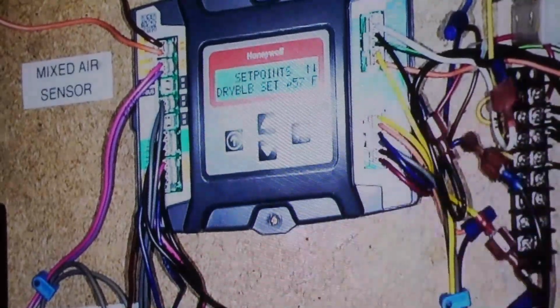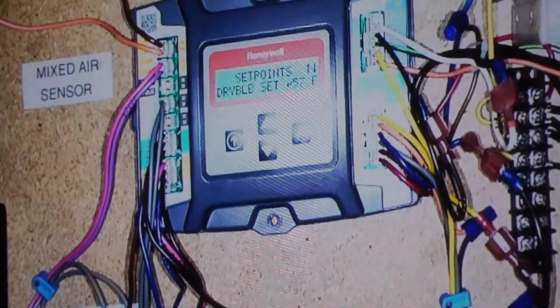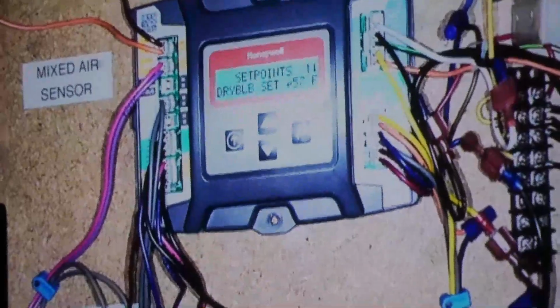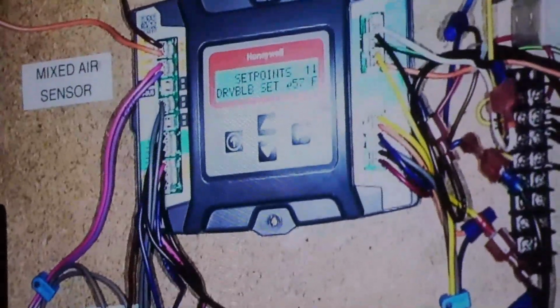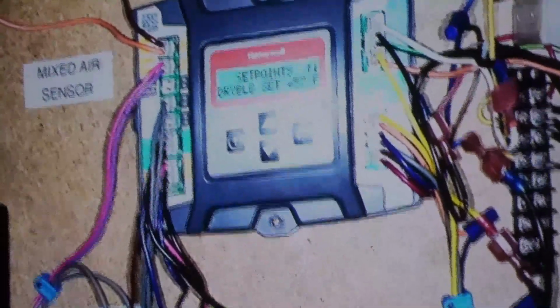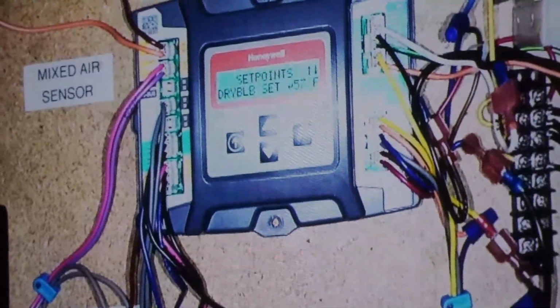The dry bulb lockout set point. So that's my economizer lockout. Alright. If I took this out and wired in an enthalpy sensor, it would immediately ask me what curve I want to be on. But since I've got a dry bulb sensor, it's looking at only temperature.